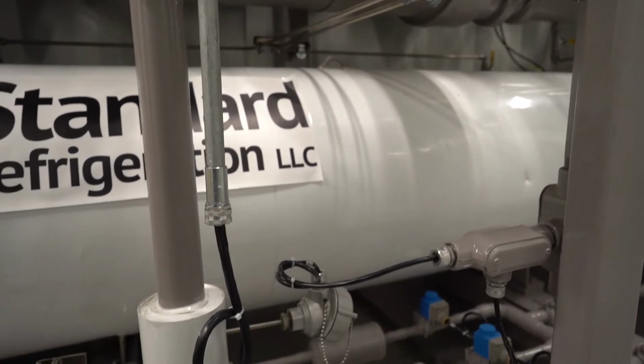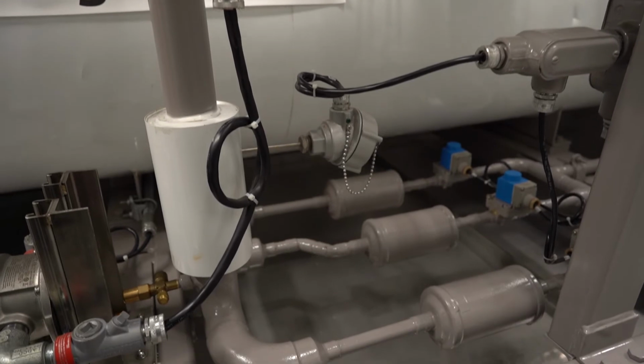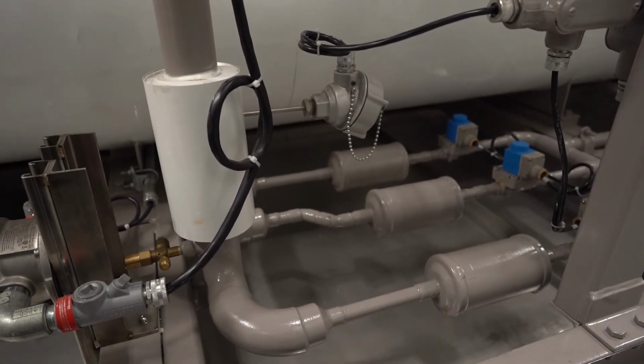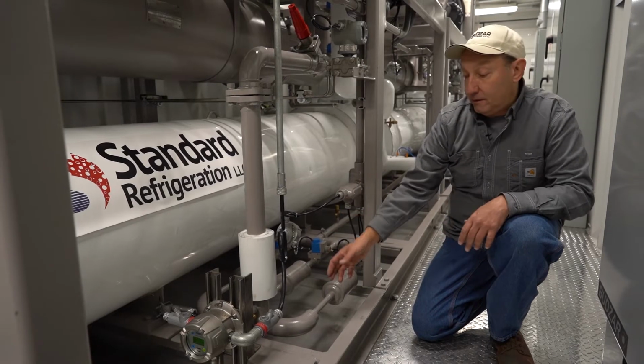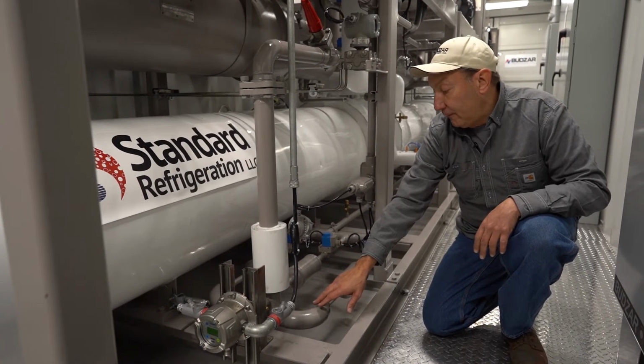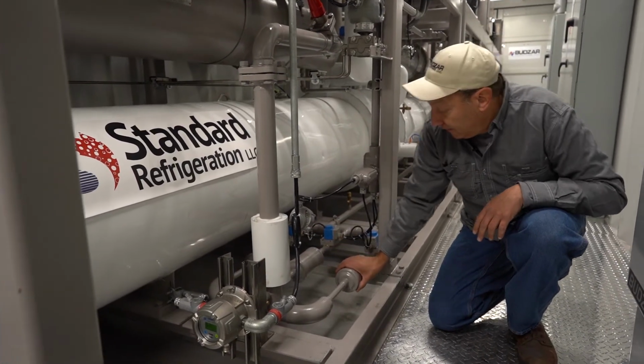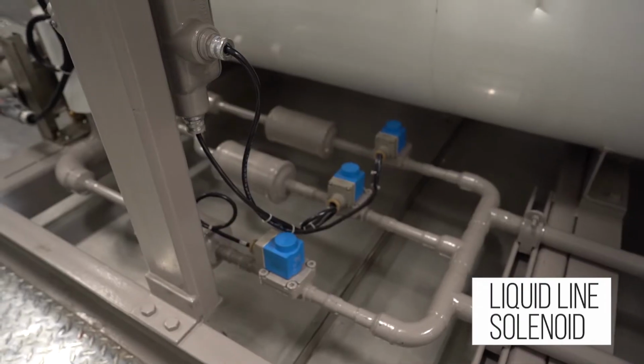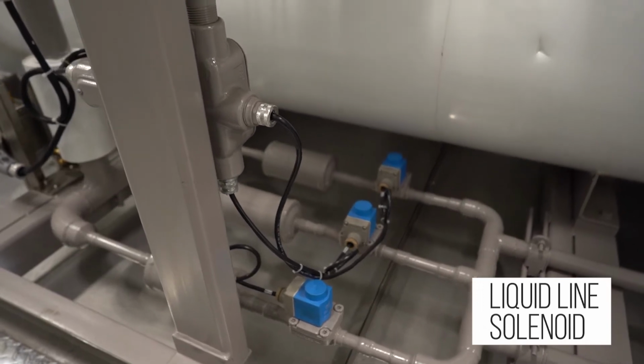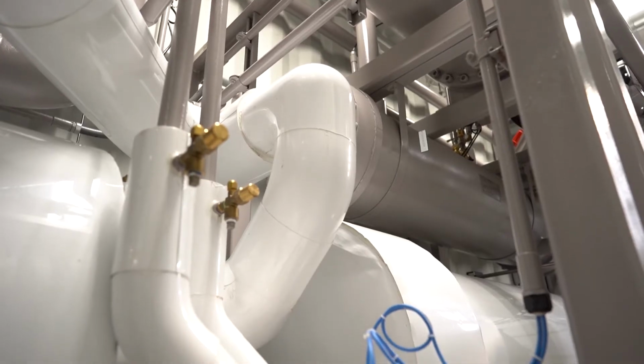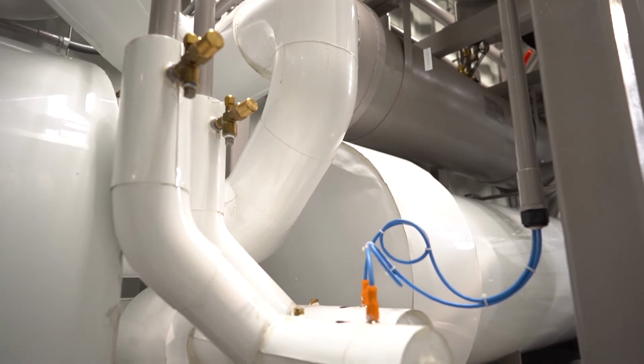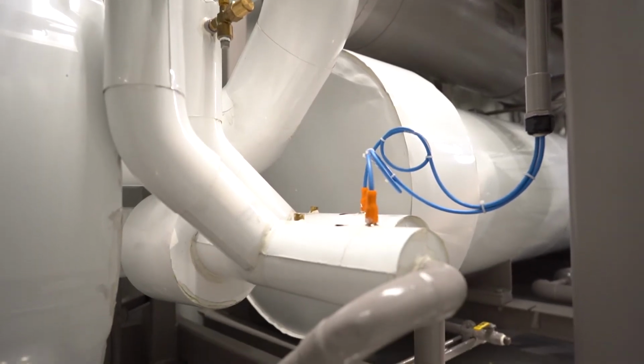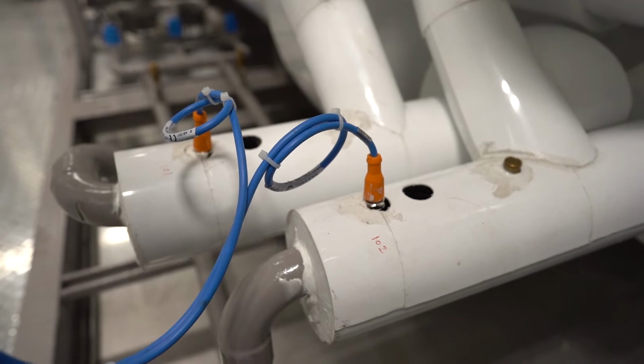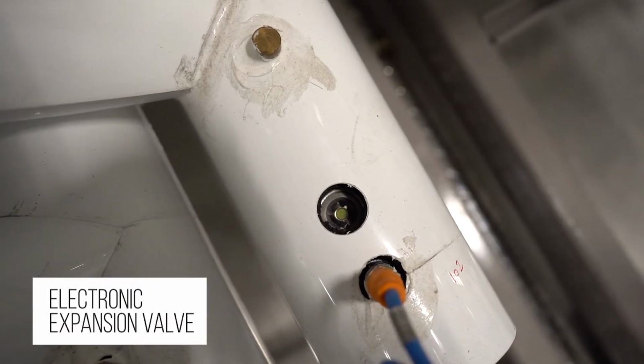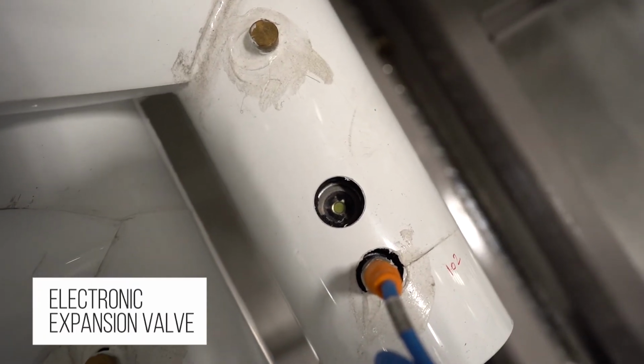The liquid line goes down here. Again, we have some more service valves for pressure gauges, things of this nature, pulling a vacuum, evacuating the system, several uses for the service valves. Then we have our liquid filters. We have our liquid line solenoids. Again, a couple more service valves for pressure gauges. And then we go into the electronic expansion valves. These are controlled by the Danfoss control boards in the control panel. And they have little sight glasses, and as usual, you're looking for a green indicator for a nice dry system.